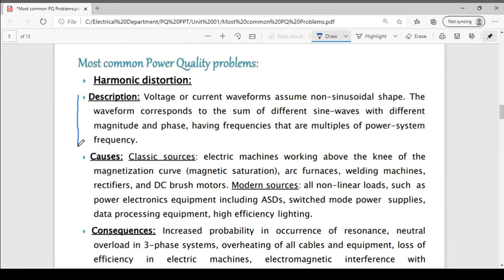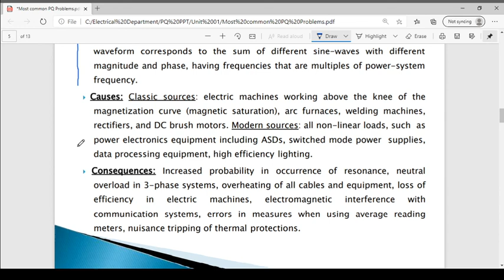So what are the consequences? It increases the probability of the occurrence of resonance, and causes neutral overload in a three-phase system, neutral shifting, neutral carrying current, and overheating of cables and equipment. There are I2R losses and loss of efficiency in electrical machines, resulting in increased heat and insulation failure. There is electromagnetic interference with communication systems, errors in measurement, and nuisance tripping of thermal protections, and failure of circuit breakers and relays, causing interruption or outage in the electrical power system. So these are the effects of harmonics on power quality.